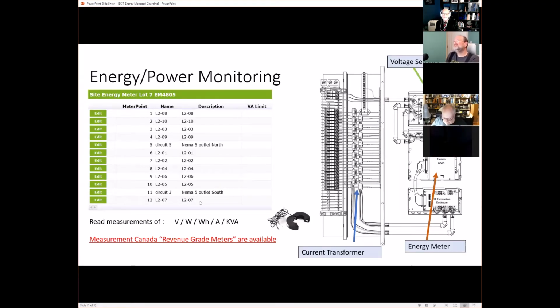Then we really get into energy and power monitoring. The picture here is again a breaker panel, and on the right-hand side you can see all these things called CTs, current transformers. They look like a donut, and they clamp over top of the wires going to the charging stations or to the loads. They have some wires running out of them that go to the actual energy meter. That energy meter will keep track of a bunch of measurements. The ones that we found we were using were volts, watts, watt hours, amps, and VAs or kVAs, which are very similar to watts, and we won't need to get into the difference, but they're very similar to what the watts are.